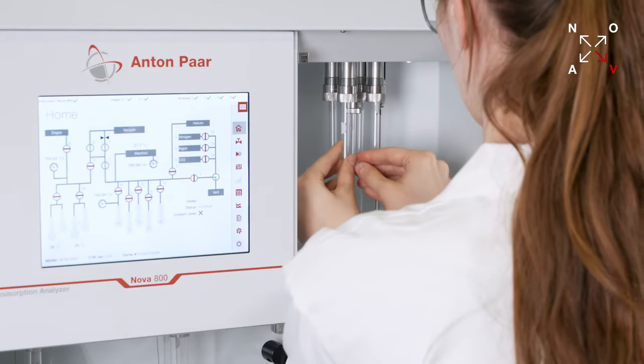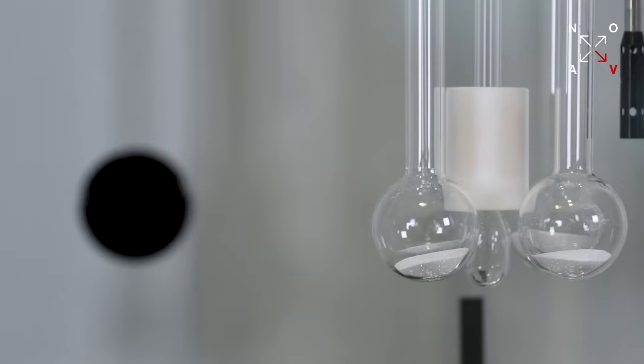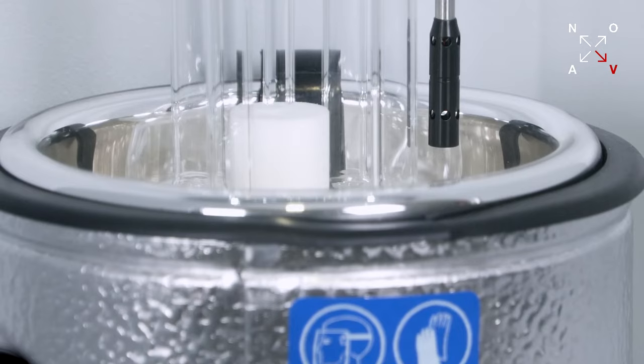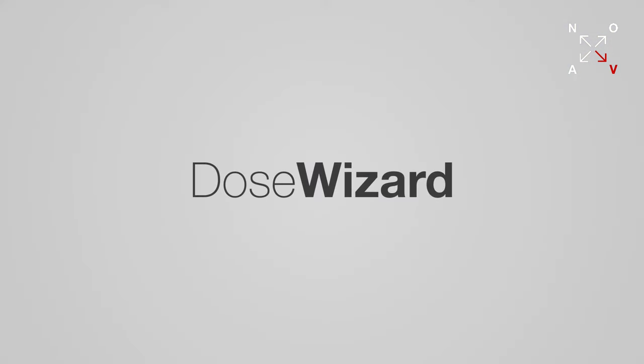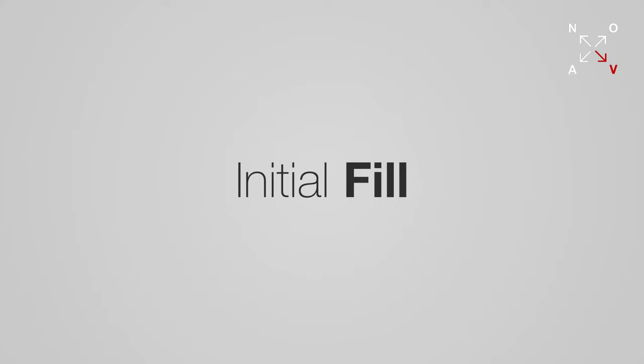This velocity is achieved by a synergy of features. The Nova mode reduces analysis times by utilizing sample cells that are pre-calibrated, and additionally, Nova mode is helium-free, allowing you to conserve this limited, precious natural resource.